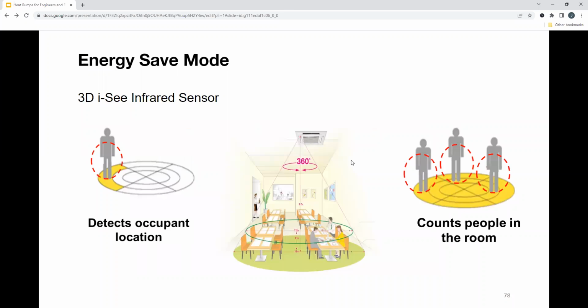Another feature that most heat pump manufacturers have is an infrared sensor. Typically you'd see this with your cassette, but what's cool about this is it actually detects an occupant in rooms. So it's pretty much an occupant sensor, but a little bit smarter than that. You can actually detect a human from your dog. What you're able to do is set it up so that if we detect a person in the space, we can either have those vanes flowing directly on the person, or if you don't like airflow going across your skin, you can also set it away from you. So pretty smart technology here. It isn't used a whole lot, but I did want to point this out. It also counts the number of people, which can help with the energy save mode function.